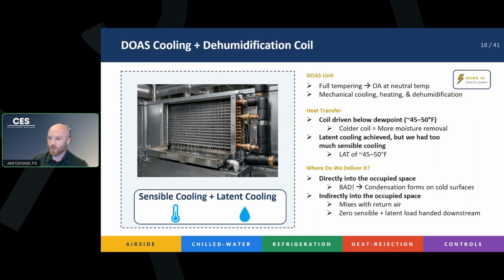latent cooling, right? But with a colder coil, we're going to overcool this, right? If we have a leaving air temperature of 40, 45, 50, that air, if you dump it directly into the space, is probably going to give you some issues, right? If that cold air blows directly onto a cold metal surface or onto a window or something, that surface in the space also gets lower than the dew point of the space temperature, and you're going to get condensation on your windows. You're going to get condensation on cold surfaces, and that definitely would be a bad problem to have. You've got to be careful with how much you overcool, and sometimes it's a balance. Or maybe you just dump it into a mixing box of a downstream coil, and then that super subcooled air mixes with warmer return air, and maybe you're not delivering that air below the dew point anymore, and you don't have the condensation risk.